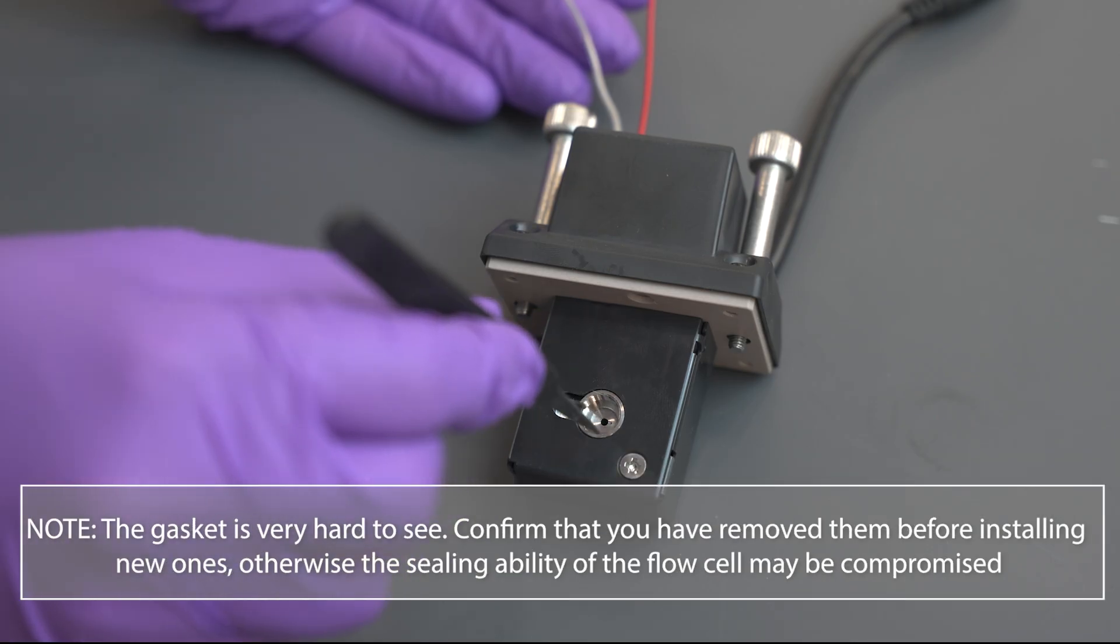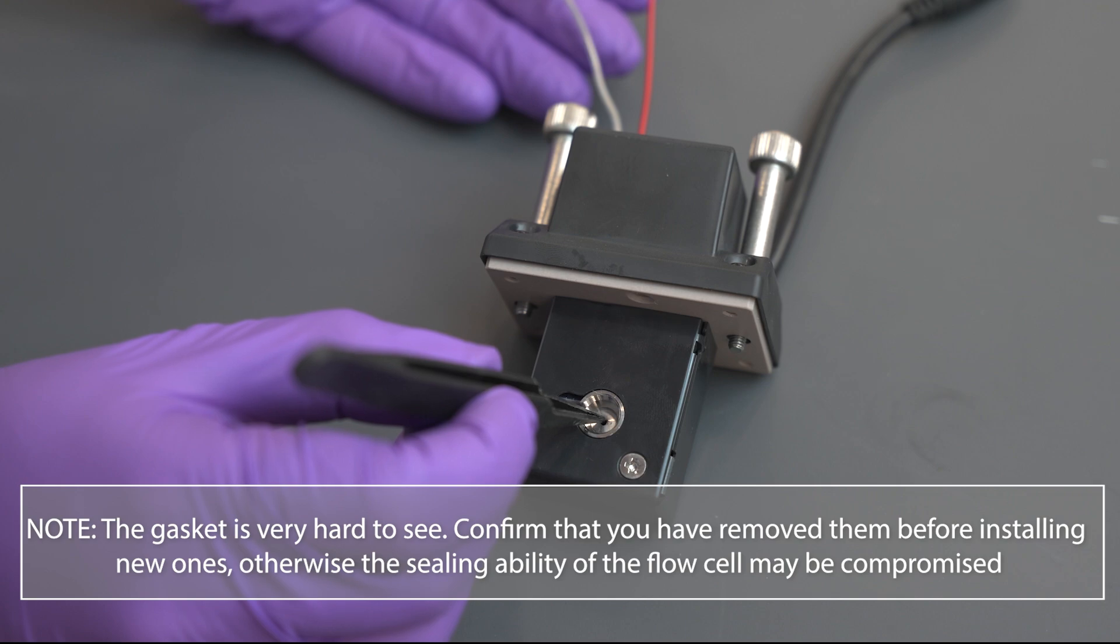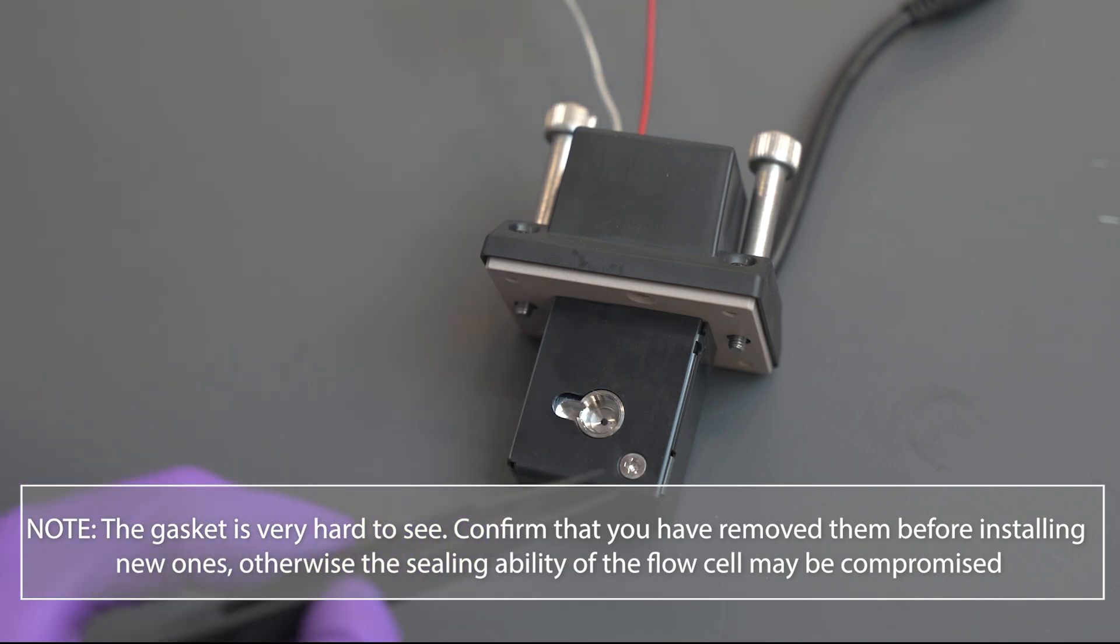The gasket is very hard to see. Confirm that you have removed them before installing new ones, otherwise the sealing ability of the flow cell may be compromised.